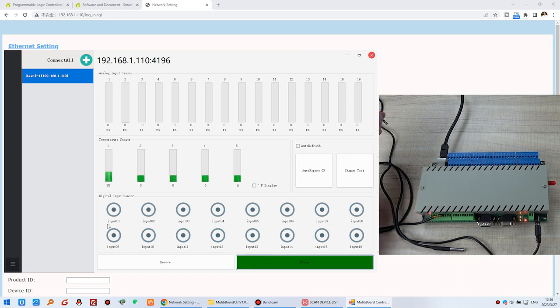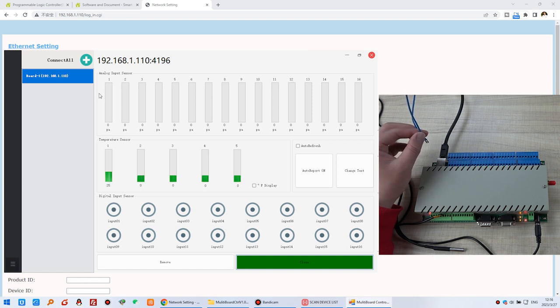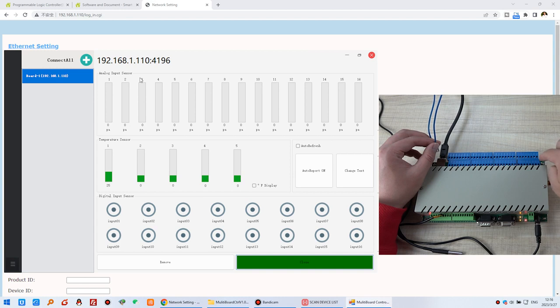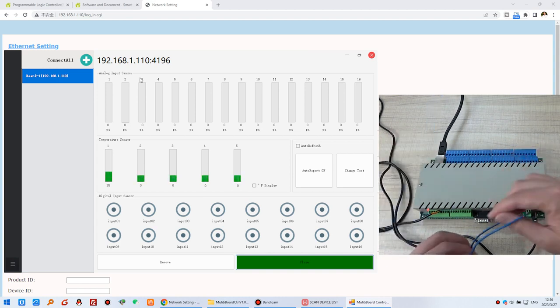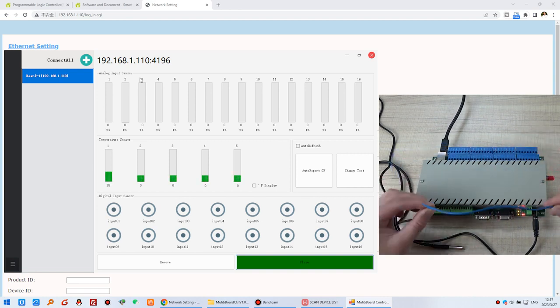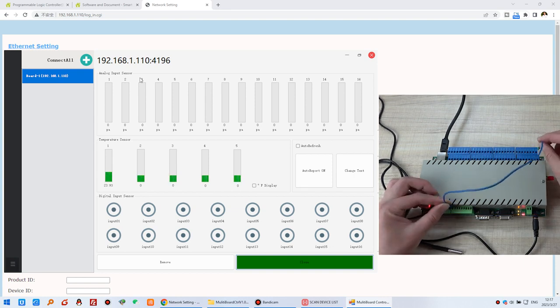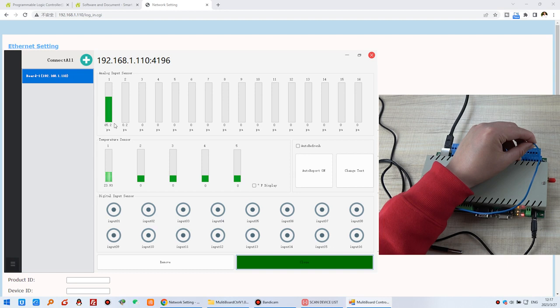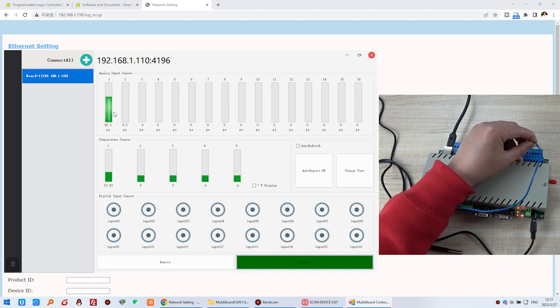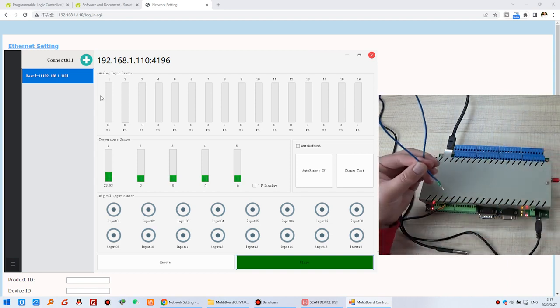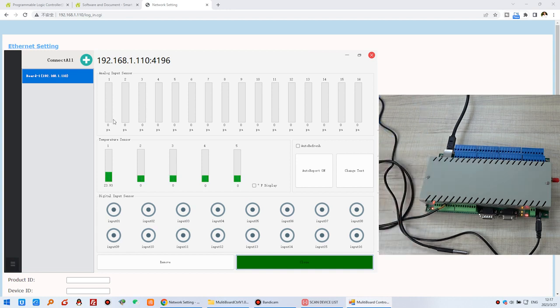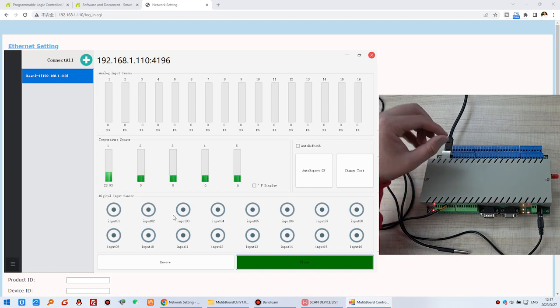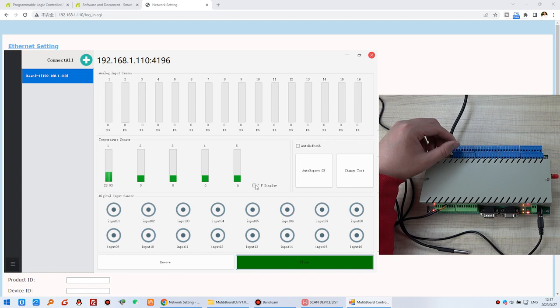I short channel 16 and it turns green; removing the cable recovers it. This is for testing dry contact sensors — you can connect a smoke sensor, door sensor, or any dry contact sensor. For the analog sensor, the input range is 0 to 5 volts. I connect 3 volts for a test and you can see it shows 65%, meaning approximately 3.3 volts. When I remove the cable the analog value returns to zero.